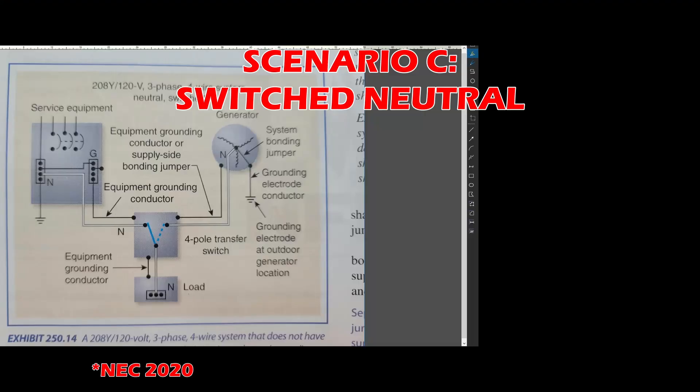In this scenario, the neutral wire gets disconnected completely at the transfer switch. Since the neutral wire gets disconnected, this generator setup is considered as a separately derived system. This means this configuration is treated as two independent electrical systems.